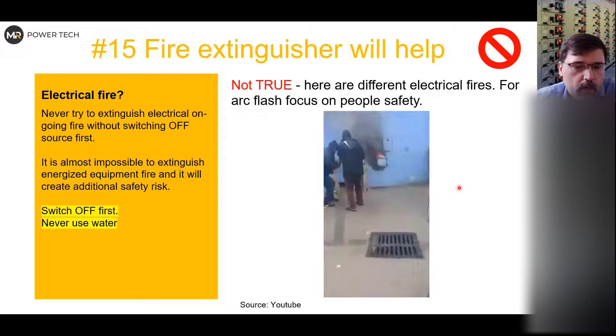Next one, which I really like, and I think I have to point it out, is that people tend to extinguish electrical fires with extinguishers. Generally they try to do something while it is still energized. So this is not true. You cannot really extinguish an electrical fire, but I need to explain two things. When we talk about an electrical fire, it is a fire caused by electricity, and then, for example, the electricity is switched off and you just extinguish the fire itself, or you try to extinguish an arc flash. The first one is possible to do, the second one is impossible to do, and you put yourself in danger. So you always have to switch off the power.